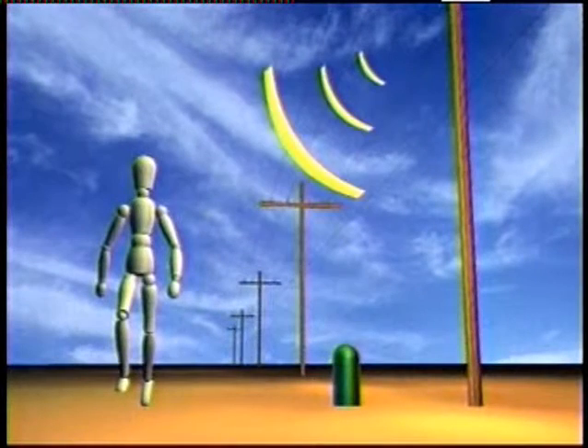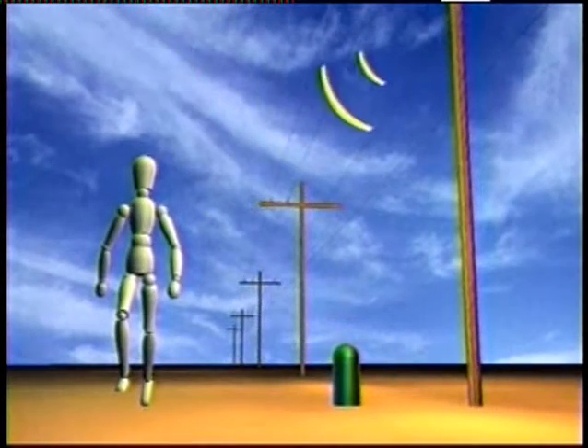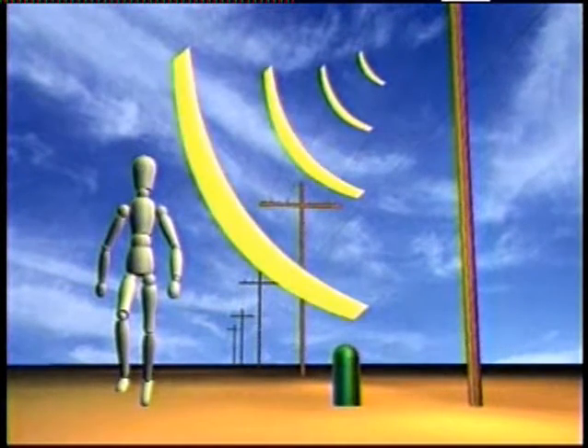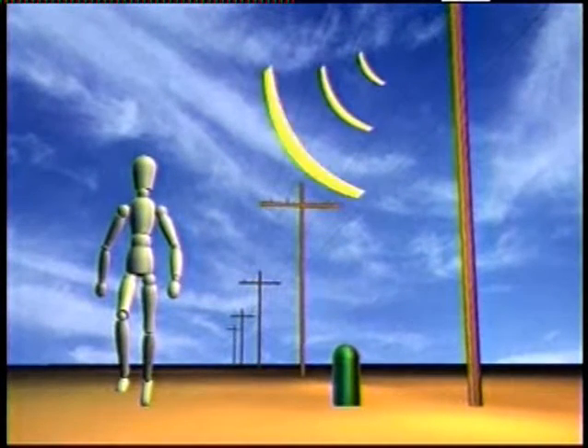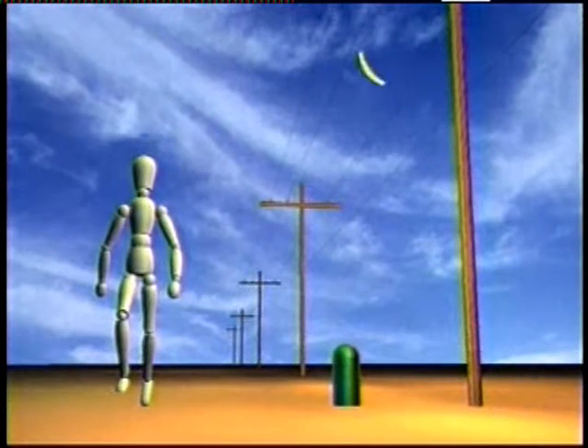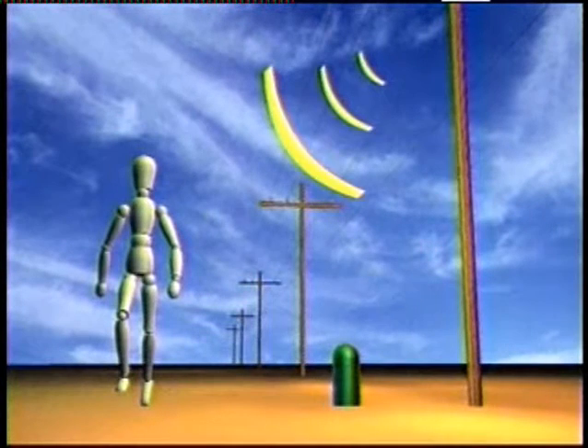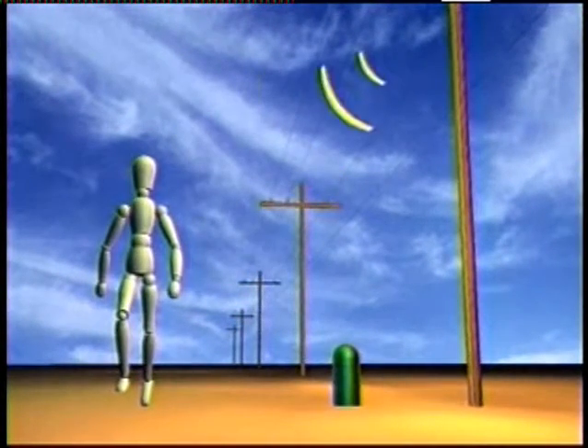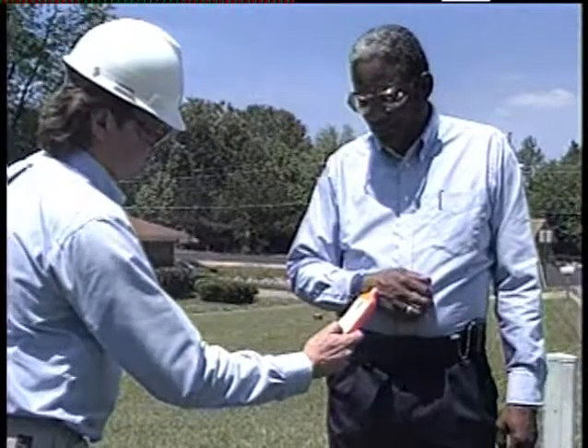These indications are caused by the electrical field between the power line and nearby conductive objects. These are not false indications. The indicated voltage does exist on the objects. The voltage is coupled through a very small amount of capacitance and at a low frequency, so there also exists a very large amount of opposition to the coupling. To us, this means there is almost no capability to produce damaging current flow, so the observed voltages are not dangerous. They are also very easy to remove.